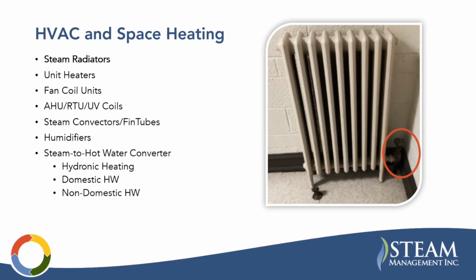First of all, in HVAC and space heating, you have steam radiators. These are typically used to directly heat spaces through radiation in a building or room. They're typically found in older buildings and residential buildings, used for heating rooms in schools, offices, and historic buildings. They're sized based on their EDR—equivalent direct radiation—so you can go around an old steam-heated building, sum all the EDRs for the different units, and use that to estimate the building's heating load. The manual steam valve for the radiator is circled in red there—I wanted to highlight that because we'll talk about thermostatic radiator valves a few times, which is an opportunity to modulate the steam flow to these units automatically based on space temperature, a good efficiency opportunity.